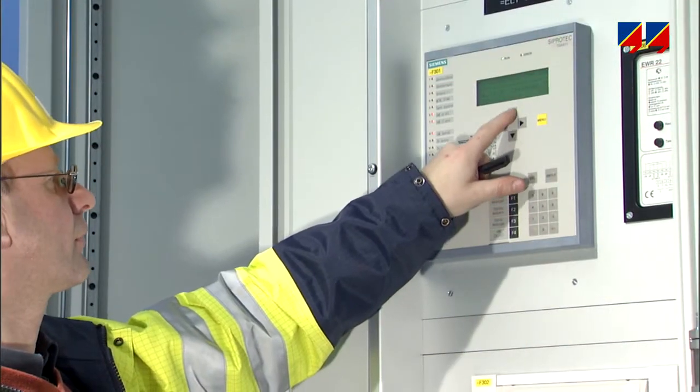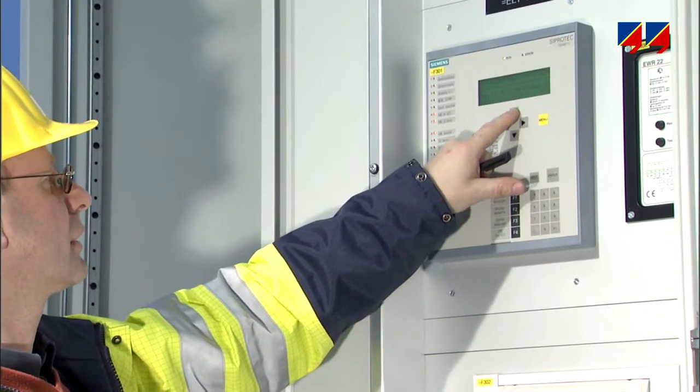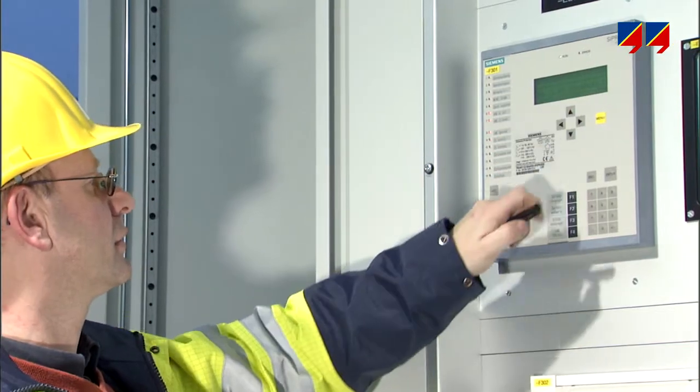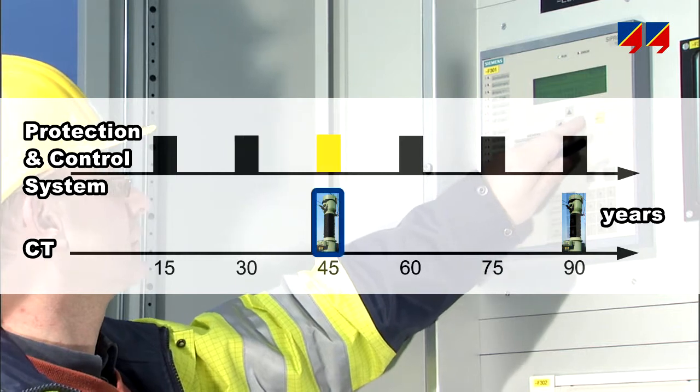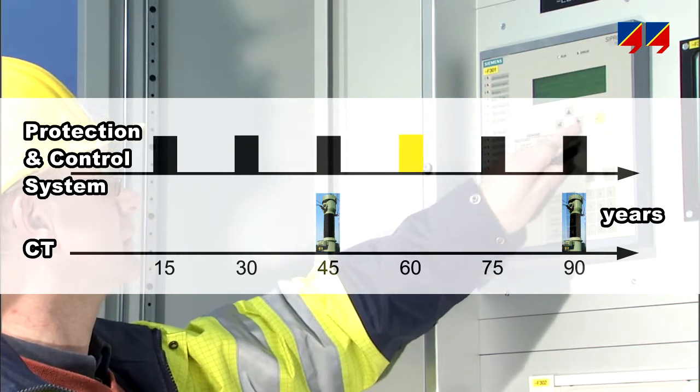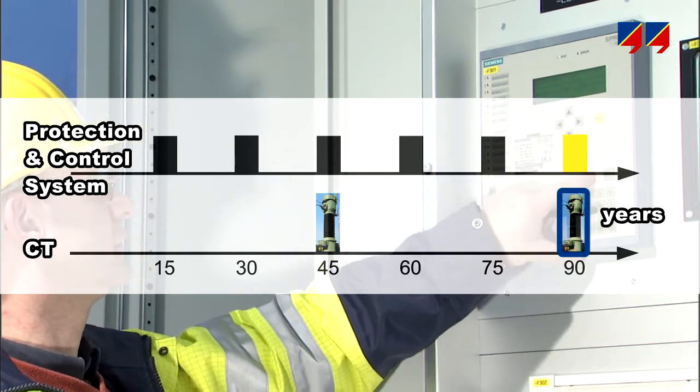CT circuits are rechecked when a plant is modified, for example, when new protection and control systems are installed. These systems have shorter life cycles than a CT, so such changes may occur several times during its lifetime.